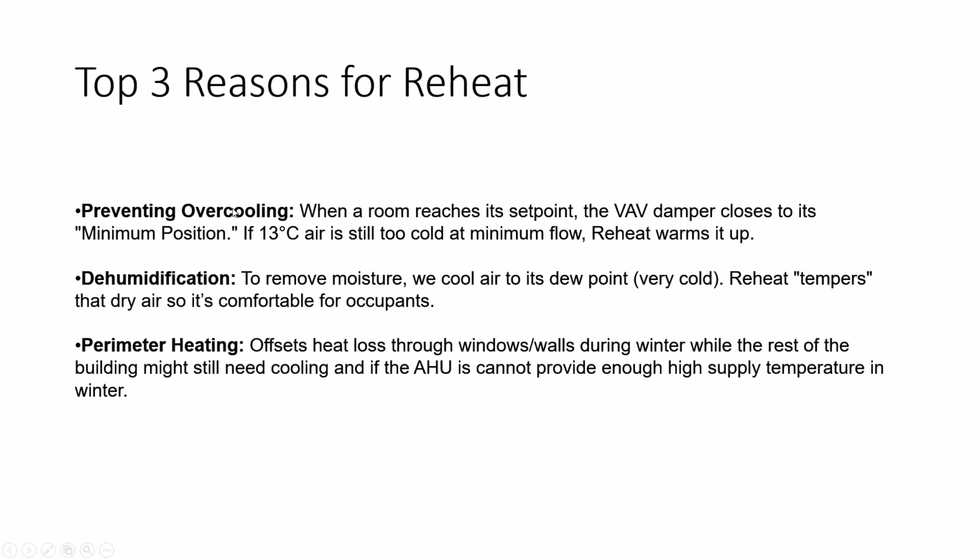There are three main reasons. One, as I have already discussed, when the room reaches its set point, the VAV damper closes to its minimum position. If 13 centigrade air is still too cold at minimum flow, reheat warms it up.